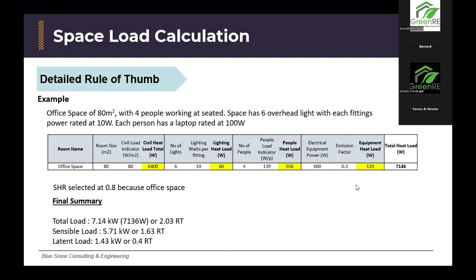So let me show you an example. Let's say an office space of 80 square meters with 4 people working, seated. The space has 6 overhead lights with each fitting rated at 10 watts, and each person has a laptop at 100 watts. So this is good, like I mentioned, for 30% to 50% detailed design. It lets you play around and understand the nature of the space. But later on, you'll probably need to do detailed engineering, especially if you're going to use some unique cooling systems, which we'll get to down the slides. So this is roughly how a typical calculation would play out.